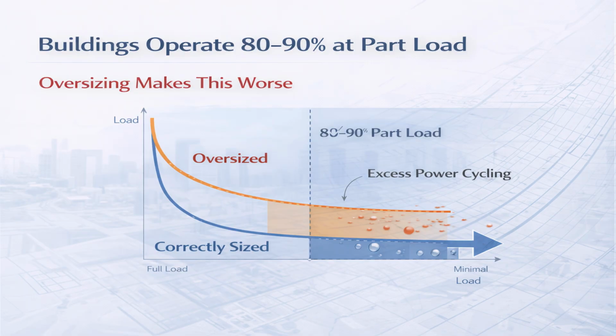One reality that is often overlooked in HVAC design is that systems almost never operate at full load. For most of their life, HVAC systems run at part load conditions, often 80 to 90% of the time. Now, let me give you a simple site example. Imagine an office space that has a calculated load of 8 ton. Instead of selecting an 8-ton unit, a 12-ton unit is selected to be safe.